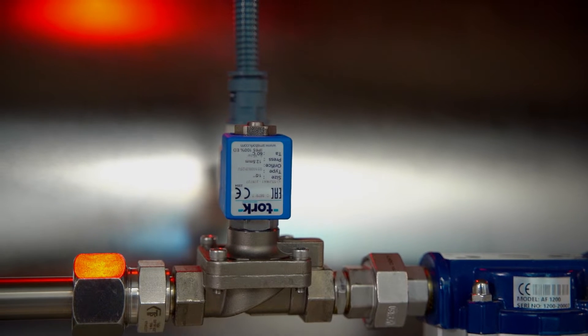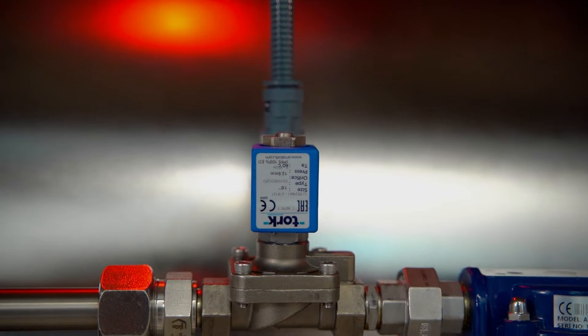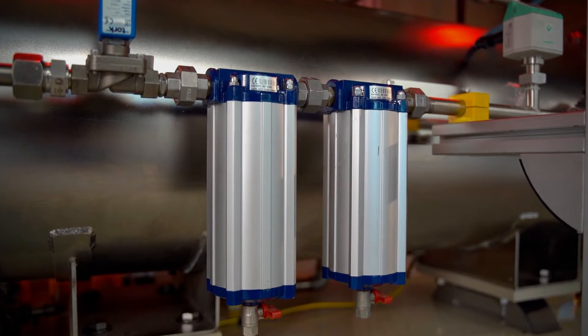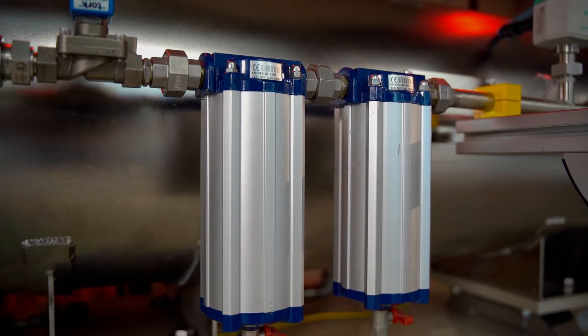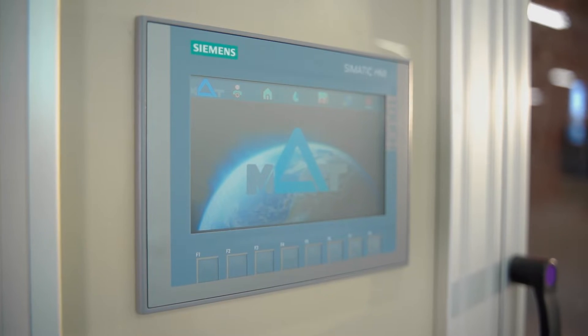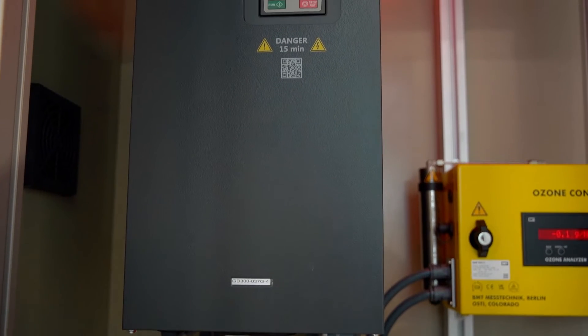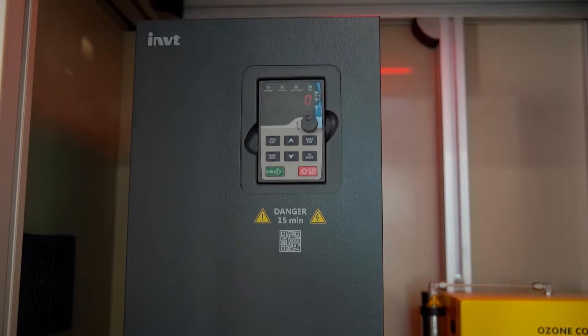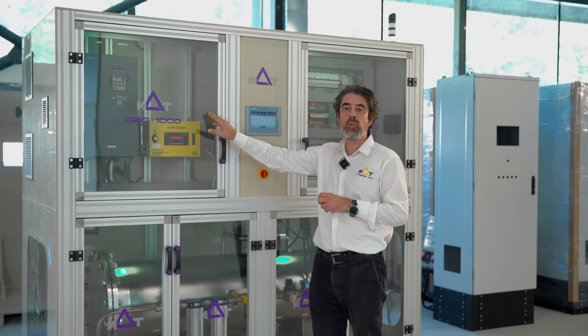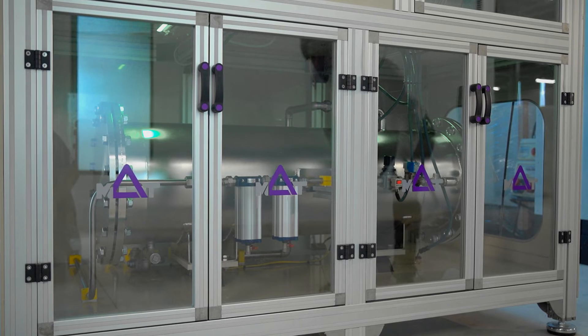We can reach up to 1.5 bar ozone outlet pressure and a concentration rate higher than 10% by weight. The PLC-integrated variable frequency driver allows us to adjust the production amount in 1% steps.